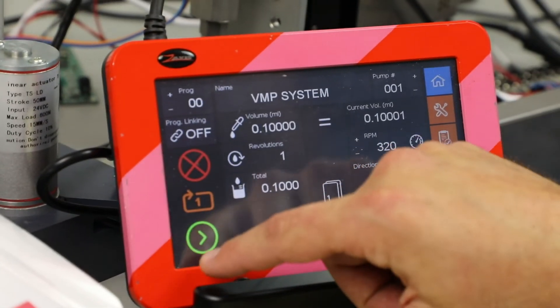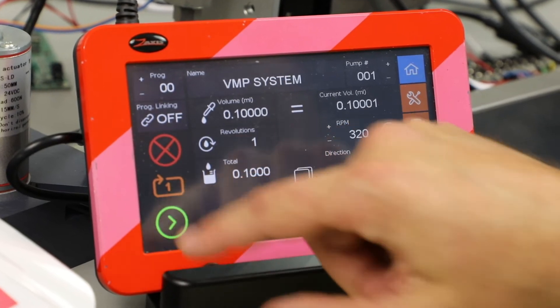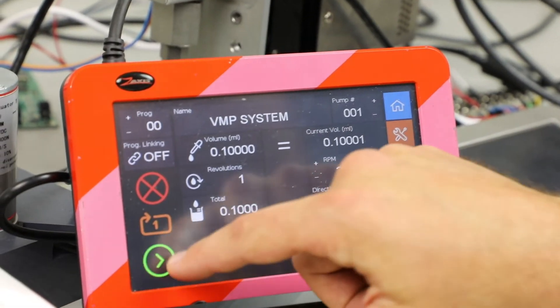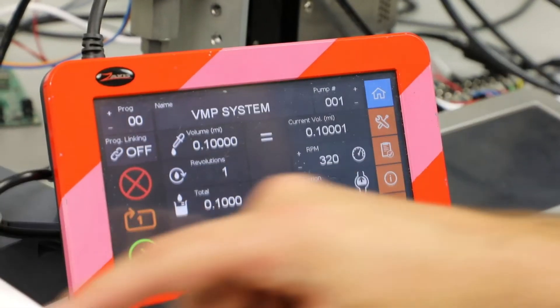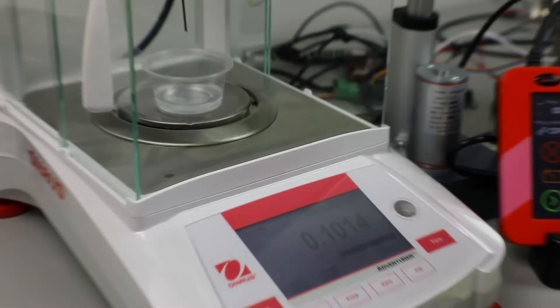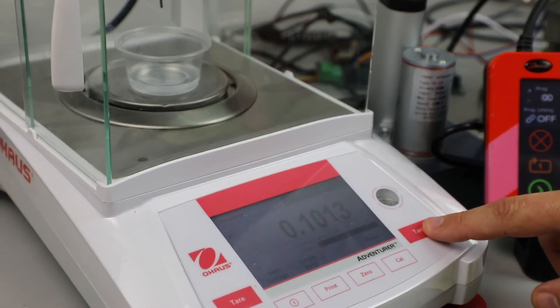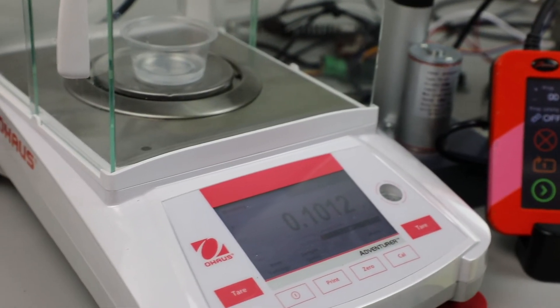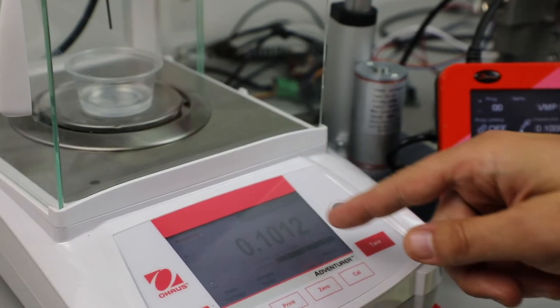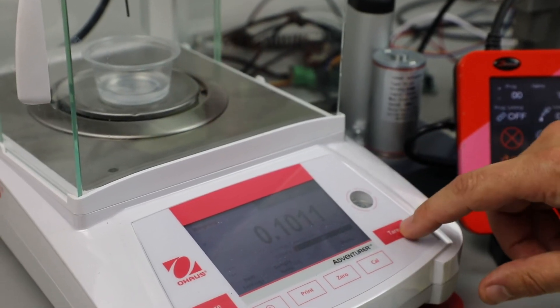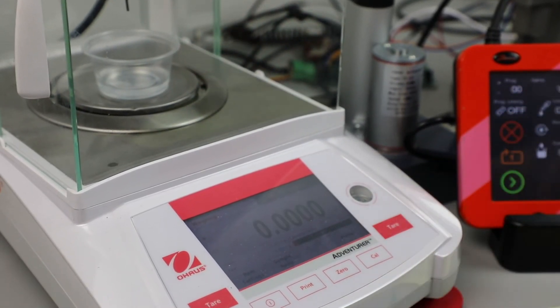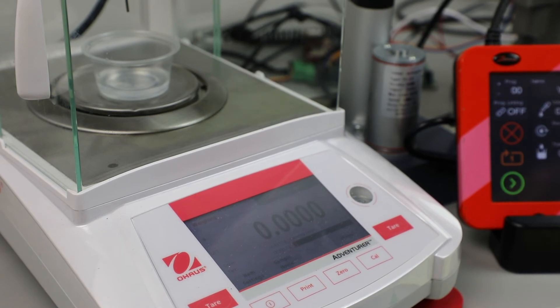So I'm going to normalize that change. And let's tare our scale. Let's observe the needle. We don't have a hanging drip. We're getting a clean eject off of it. And so without doing any touching, I'm 0.101. So I'm within a tenth of a percent. Our system accuracy is 1% full scale, and our reproducibility is better than half a percent.